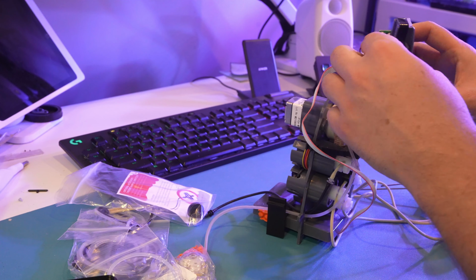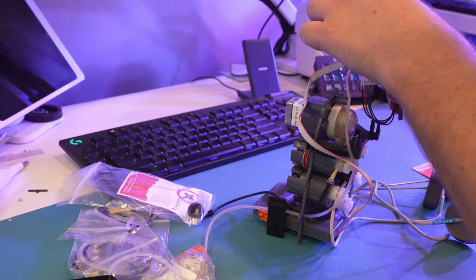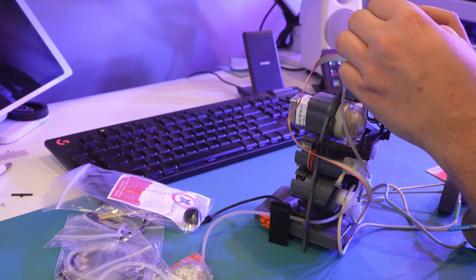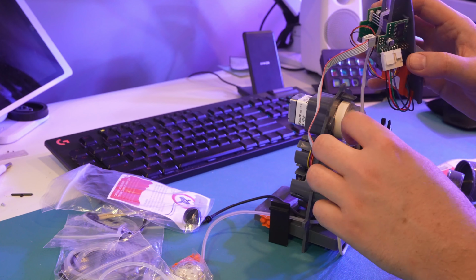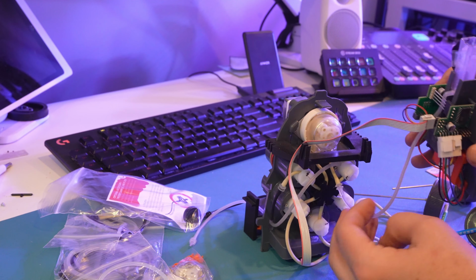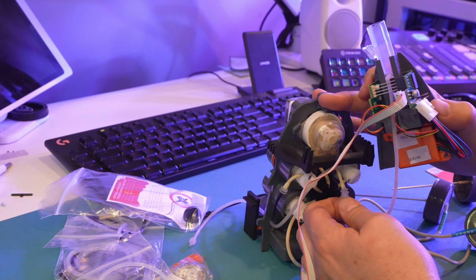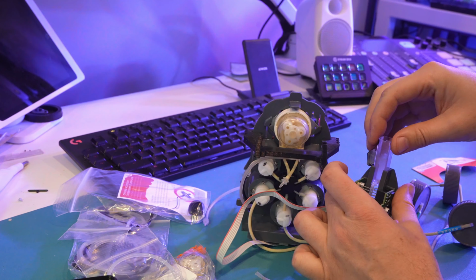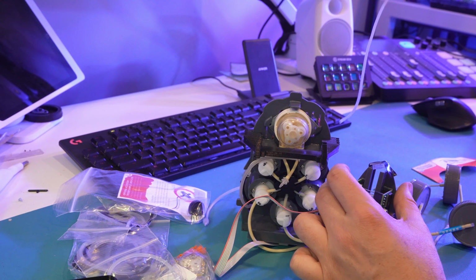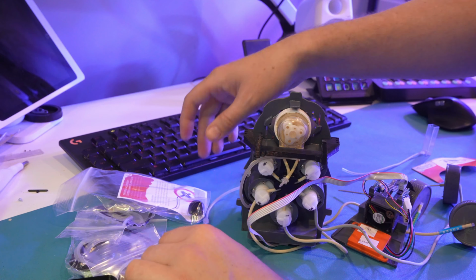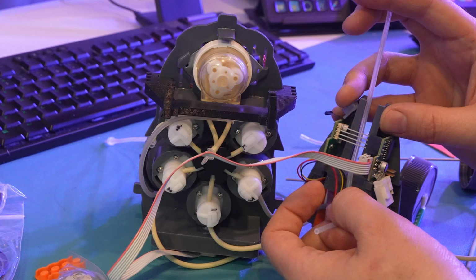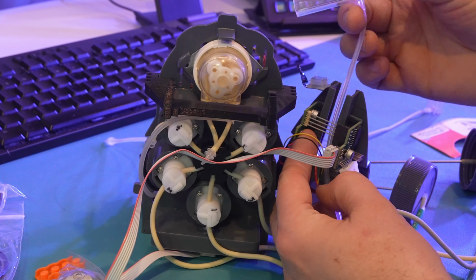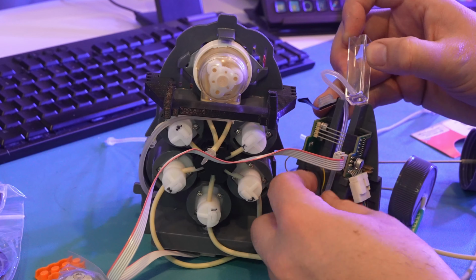Now, I'm going to start with the cuvette, so I'm going to peel up one side of the electrical tape. Pops open the lid, we should be able to slide our cuvette up. And on this, we're going to have to remove it from our pump head, so I'm just going to loosen this one off. And I should just be able to slide it up from there. So we got our cuvette out. Feed the sample line in the same way you kind of took it out. And gently slide this back in.